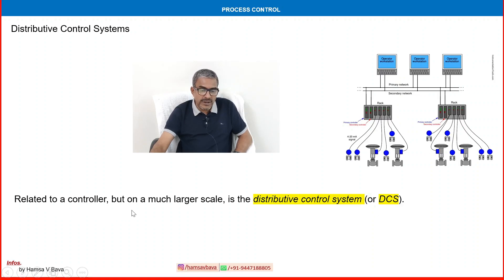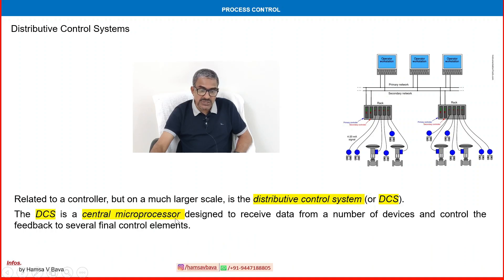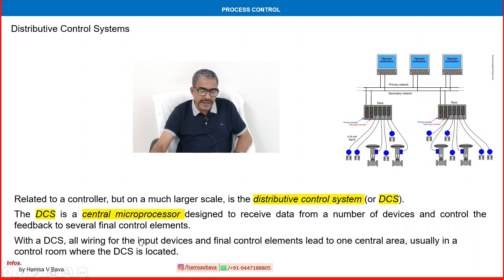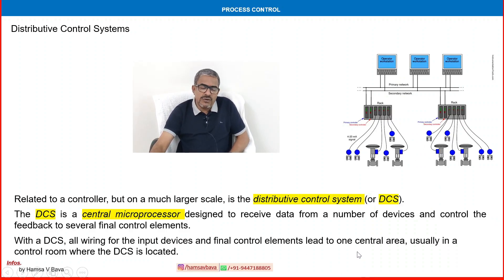Related to a controller but on a larger scale is the Distributed Control System, or DCS. The DCS is a central microprocessor designed to receive data from a number of devices — such as control valves, positioners, flow meters, sensors, and transmitters — and control the feedback to several final control elements. With the DCS, all wiring for input devices and final control elements leads to one central area, usually a control room where the DCS is located.